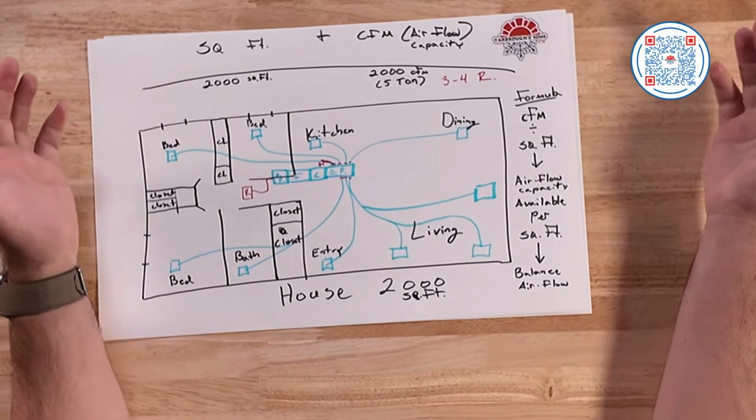I'm going to step back for a second. I talked about return air, making sure that you have plenty of return air. And I don't think I did a good job of telling what symptoms you may be experiencing or why it's important to make sure you have enough return air. So your system is designed to do 2,000 CFM of airflow.